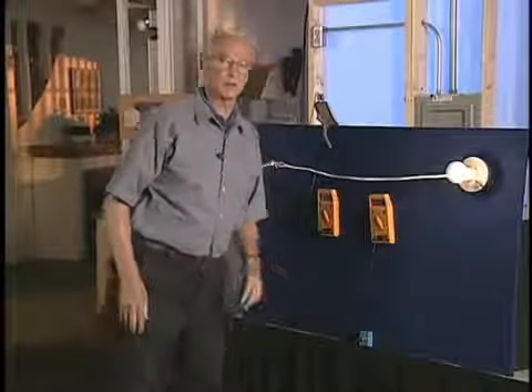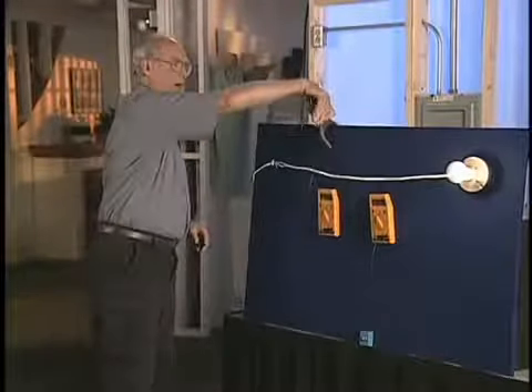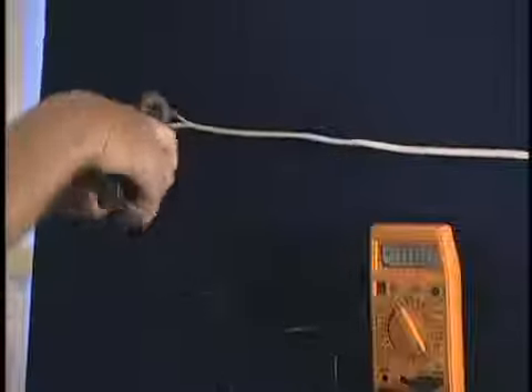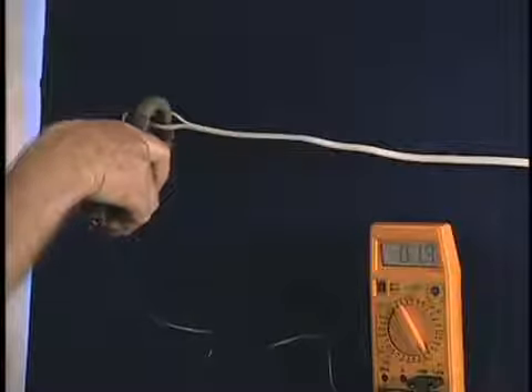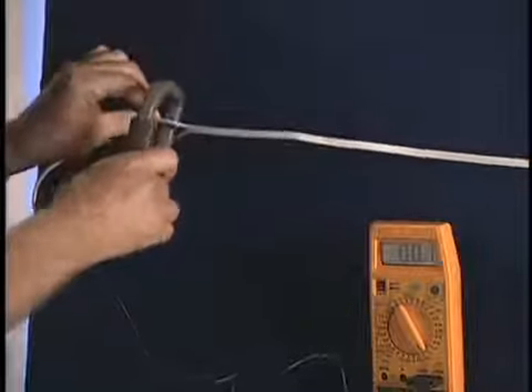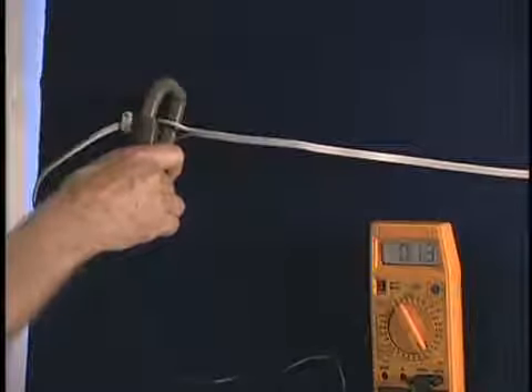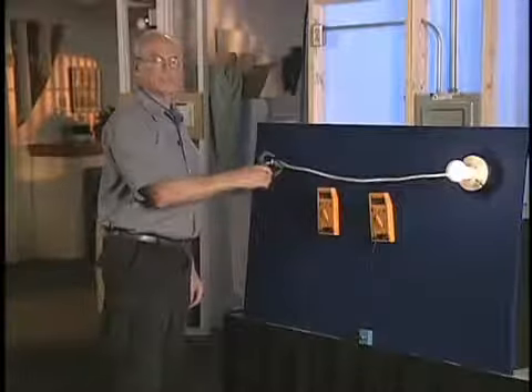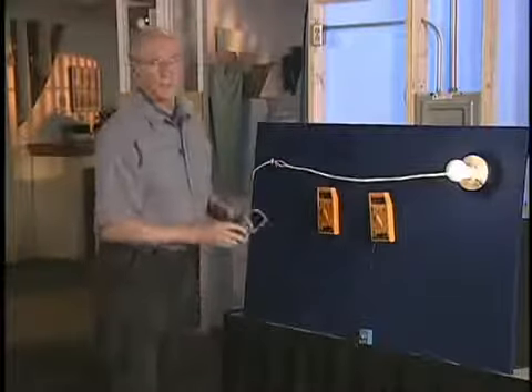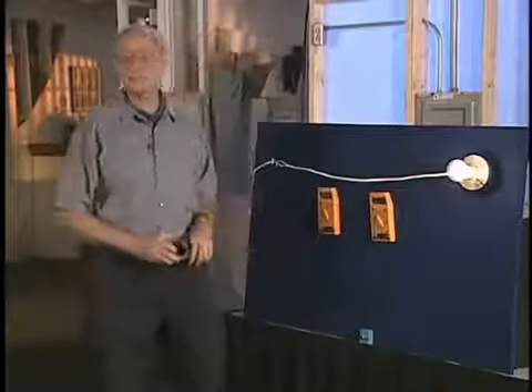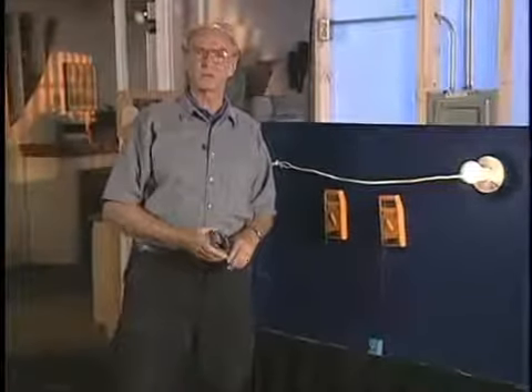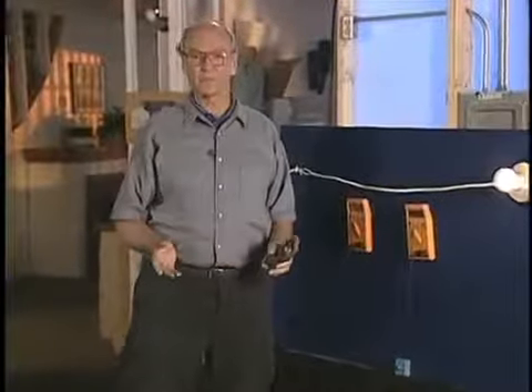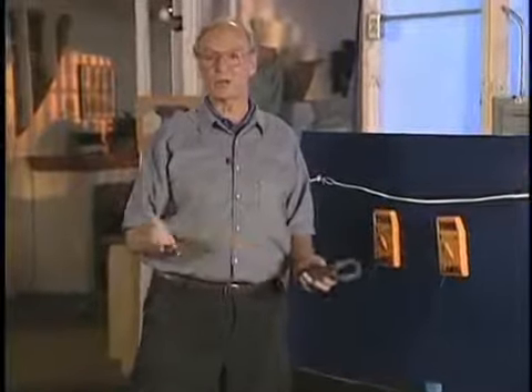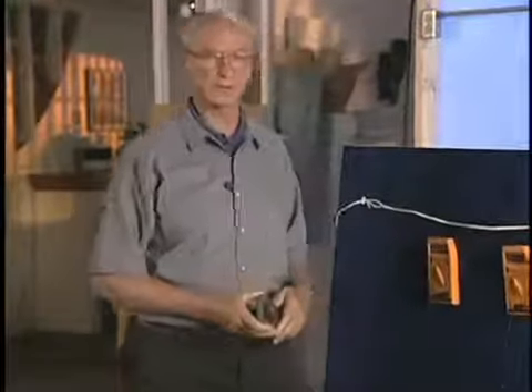To check the current, we split the zip cord and measure the hot and the neutral separately. The hot measures 1.4 amps, and the neutral the same. This is a normal situation. A net current is created when there is unequal current flowing through wires. For example, if the hot leg carries 5 amps and the neutral carries 2 amps, the net current is 3 amps. This 3 amp net current produces the same magnetic field as if 3 amps flowed in a single conductor.